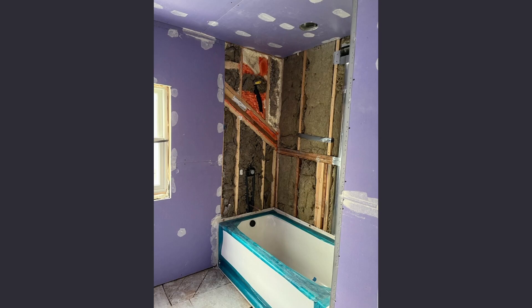Jerry writes: Hey y'all, I just wanted to offer a story from the field. We had a situation where we remodeled the bathroom and knew we needed to put a shower supply in an exterior wall in the Ann Arbor, Michigan area. The house dates somewhere around 1900 with board sheathing and a couple layers of siding on the exterior. From the inside, we taped all the gaps in the board sheathing and spray-foamed behind the new plumbing.